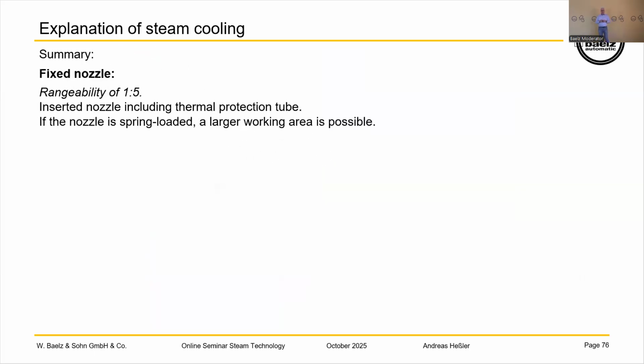Just to take a summary. Fixed nozzles, when you have a rangeability or turn down ratio, it is also the same. You can use it also as a turn down ratio. We have here a turn down ratio or rangeability of 1 to 5. It normally also needs a thermal tube to protect the piping because the water droplets are very big. And with a spring-loaded nozzle, the rangeability would be a little bit higher.